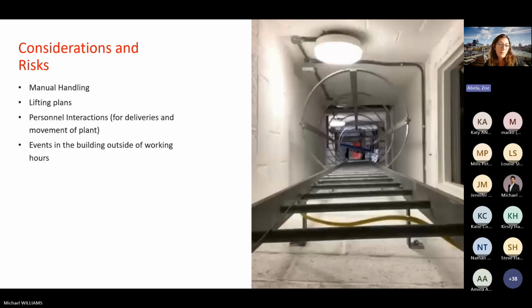The actual lowering took 2 minutes; I got my 20-year-old daughter to edit that down to the 5 seconds you can see, though it wasn't really that fast. The heaviest item was 450 kilograms, the end plate shown here. Over the weekend we lowered a total of 5 tons of equipment into the plant room using this method.